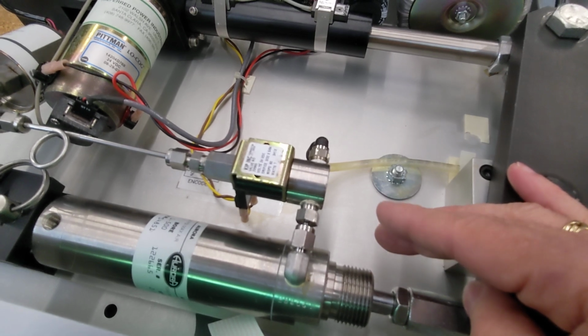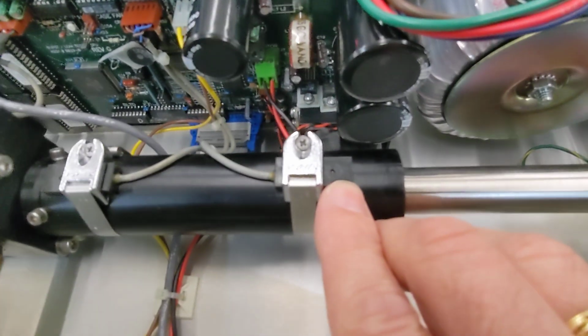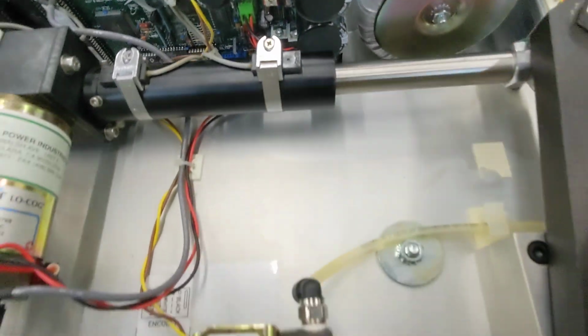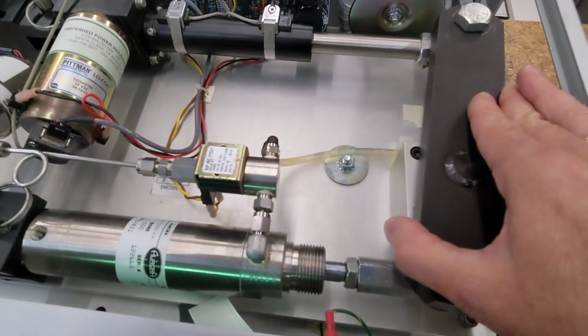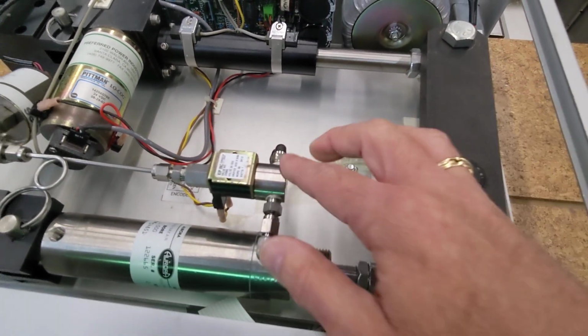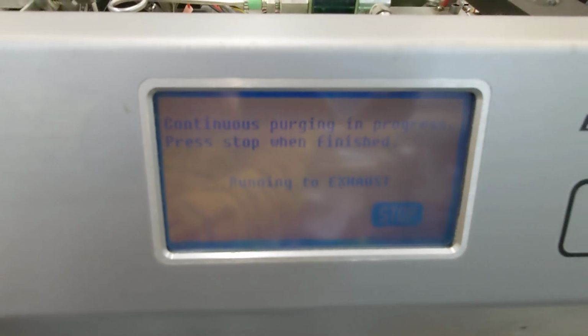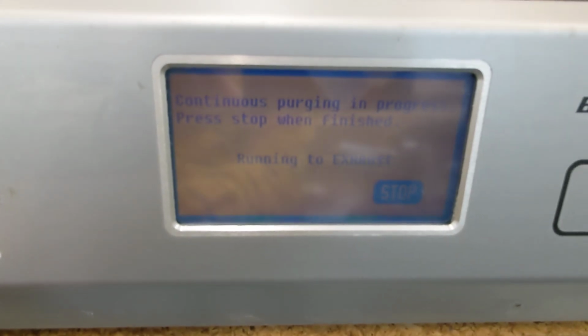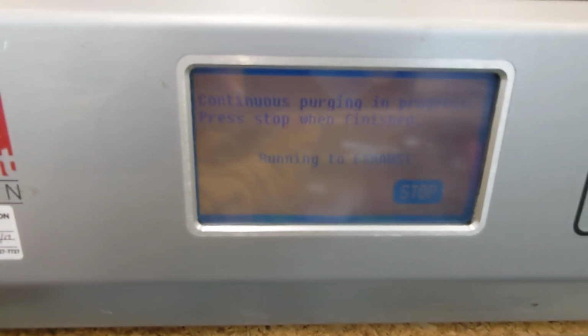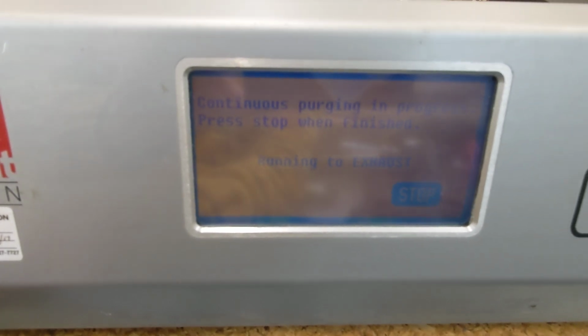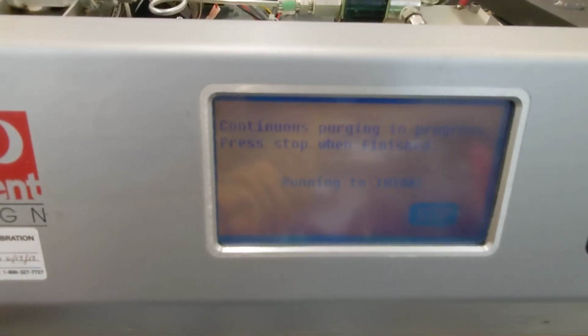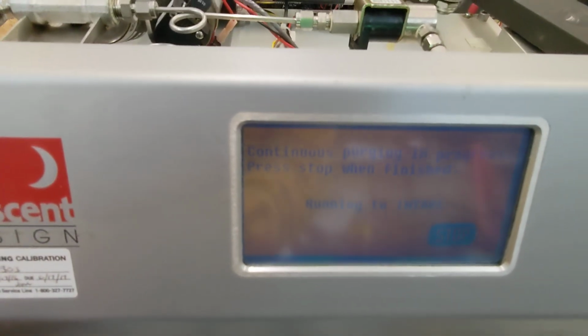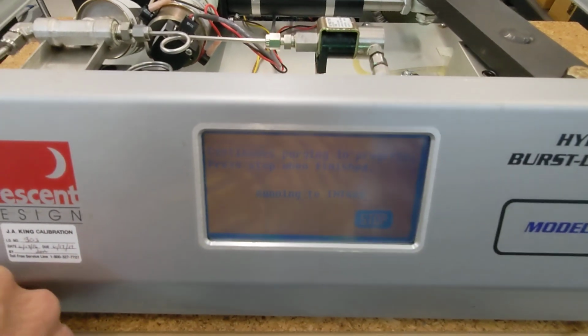So that's drawing in liquid, and now this one will go on. The motor reverses and we dispense again. Now we're dispensing out here, and if I put my thumb over this long enough, I'll probably get an error saying there's excessive pressure. Remember, they did say it was supposed to be open right now, so let's see. Well, it wasn't too much pressure, let's try it one more time.